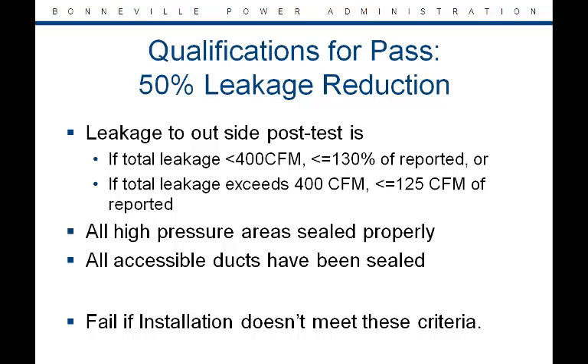If the total leakage is less than 400 CFM at 50 pascals, then the leakage to outside post-test CFM must be not greater than 130% of the CFM reported by the technician. If the total leakage is greater than 400 CFM at 50 pascals, QA measured leakage to outside must not be more than 125 CFM difference from what the technician reported.